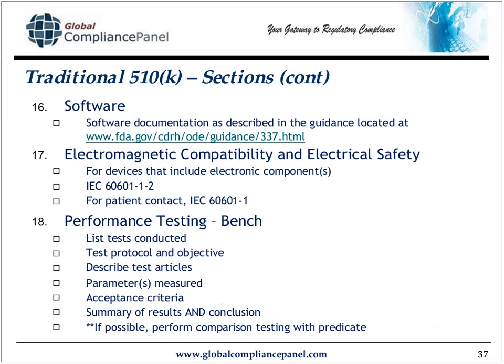Any bench performance testing, that's your in-house non-clinical testing. So you've got to make sure that your validation and verification testing is included in here. Make sure that you have a protocol and also a results document. Also make sure that in your results document, you have a nice little summary of the results and a conclusion. Depending on the nature of your bench testing, your testing may be dozens of pages long. You're going to have to include it, by the way.